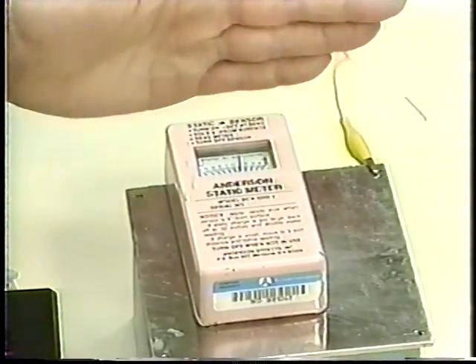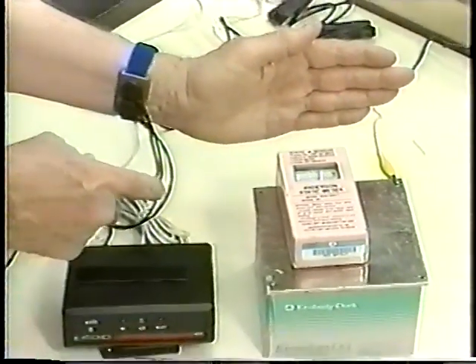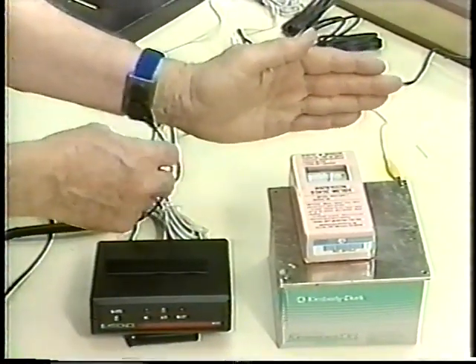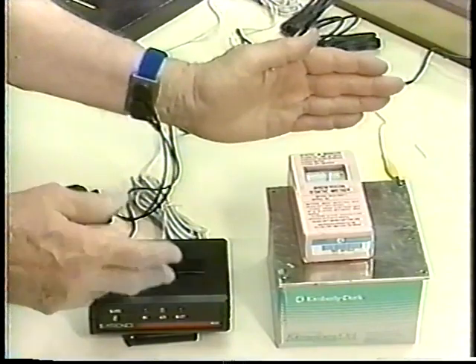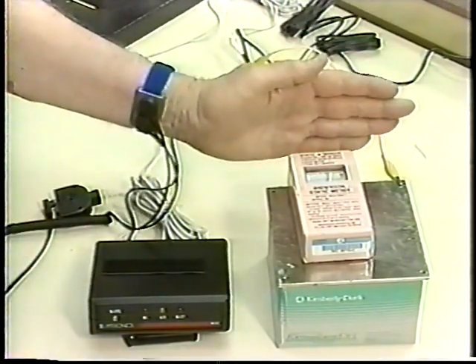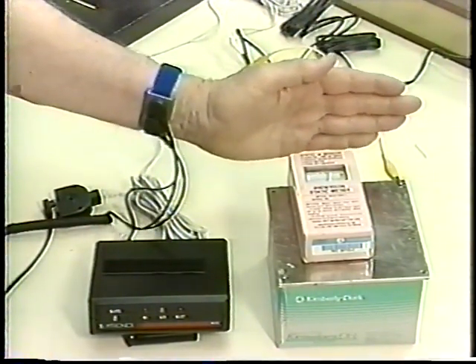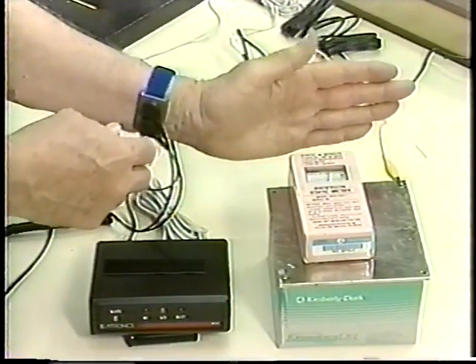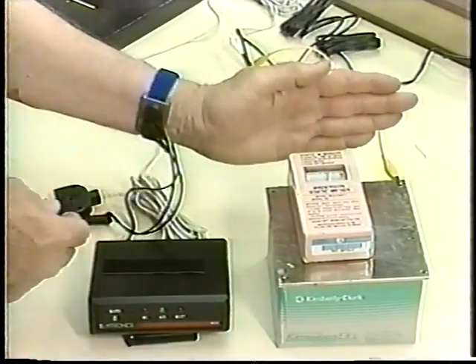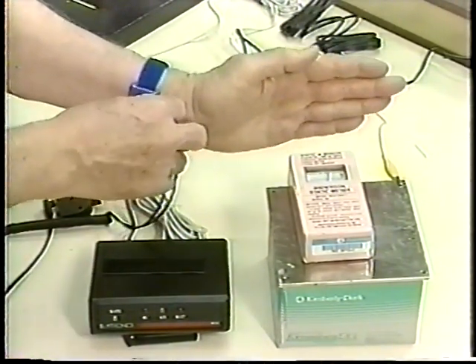The interesting thing about the continuous monitor is if the conductor should fail in one of these wires, the monitor will alarm, but you will still be grounded. Now I'm going to disconnect one. You'll hear the monitor alarm, and you'll see that the needle still doesn't move when I shuffle my feet.